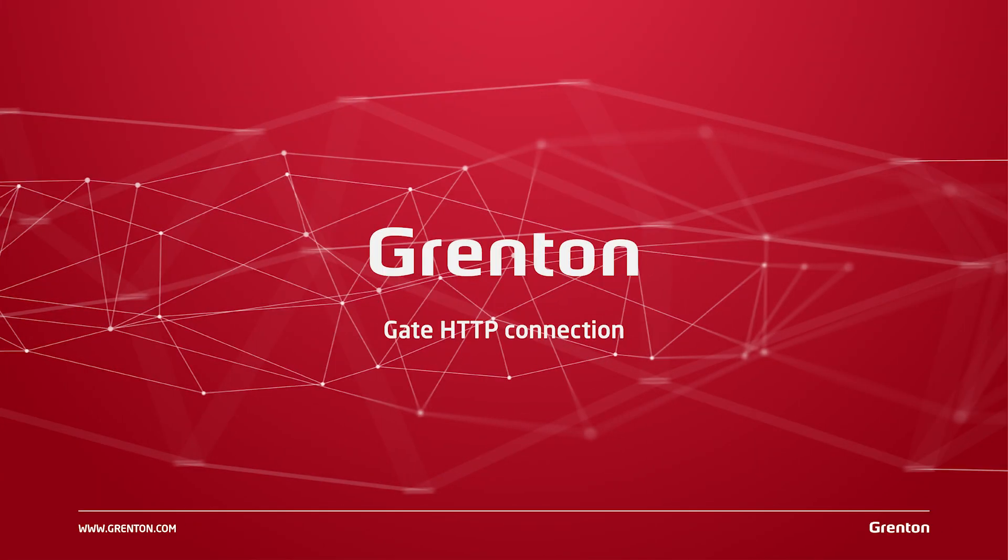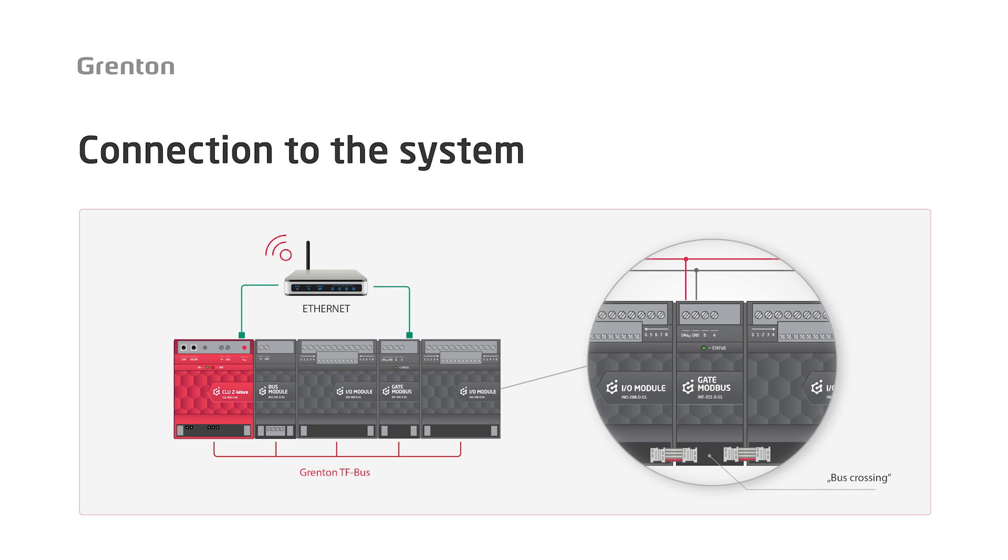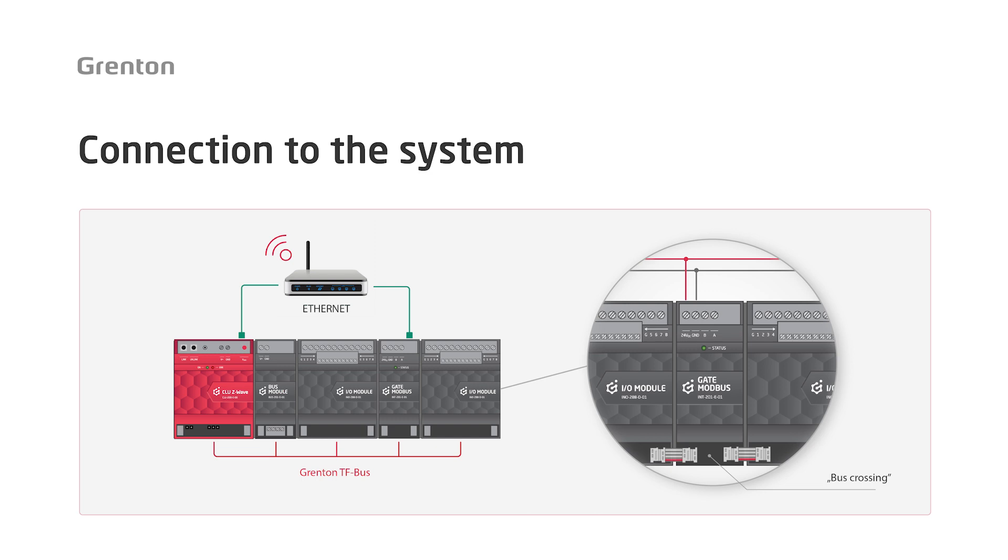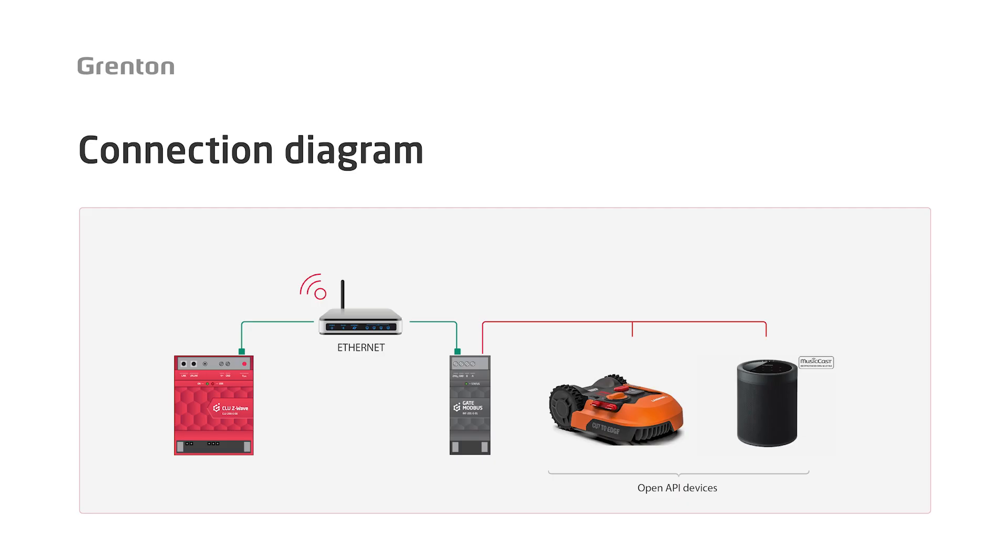The GATE HTTP module is a CLU-class device, and when connecting it to the system, we do not use the system bus for communication. Instead, it will communicate with other CLU-class modules in our system using the Ethernet port. When mounting the module in the switchboard, we connect it to the same switch router to which we previously connected the CLU module or other gate-type modules. Although the module has bus connections, it does not communicate with the system via the bus. However, you can connect the module between other modules, and through the connectors on it, communication on the bus will be forwarded.